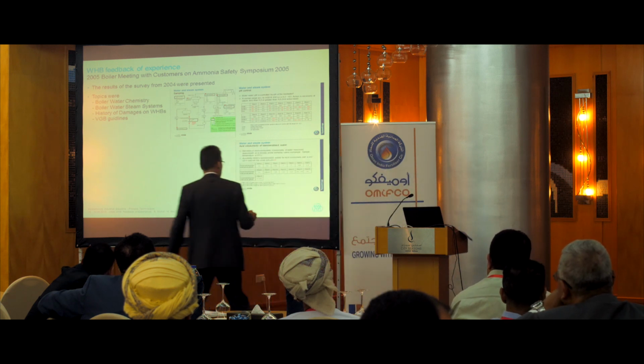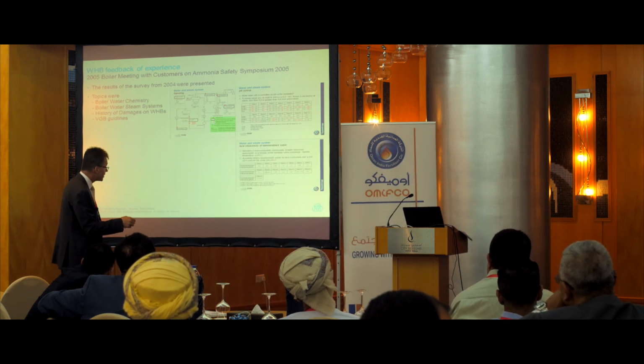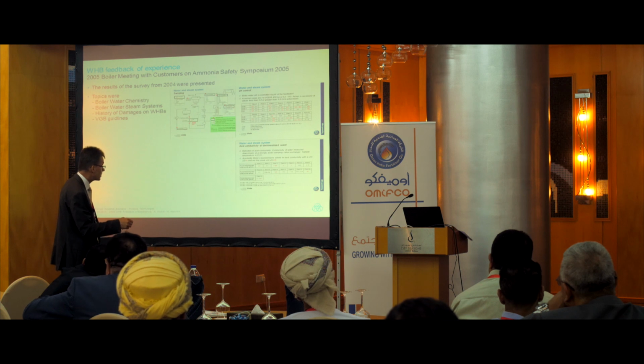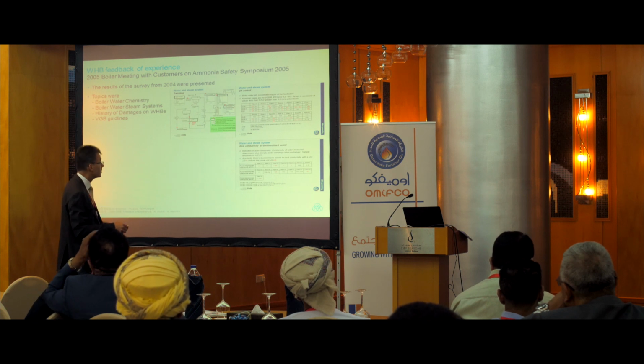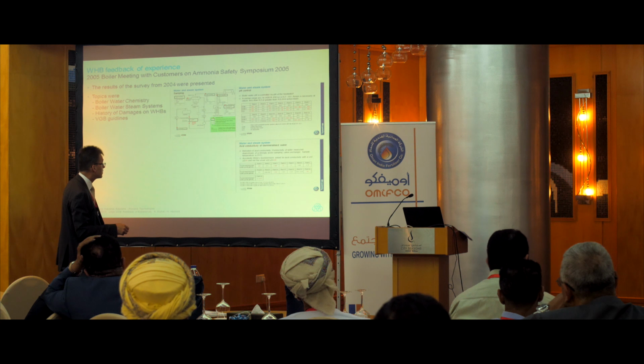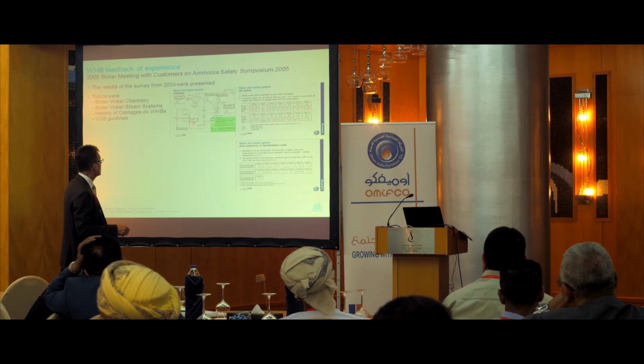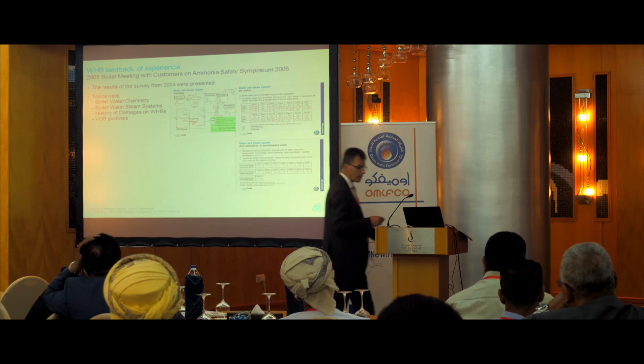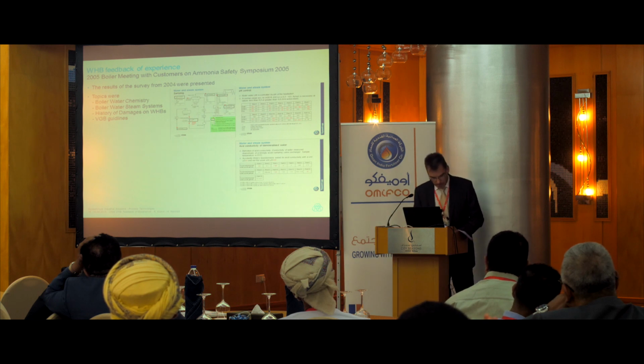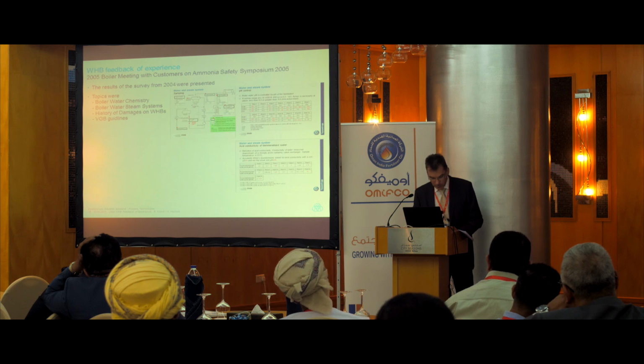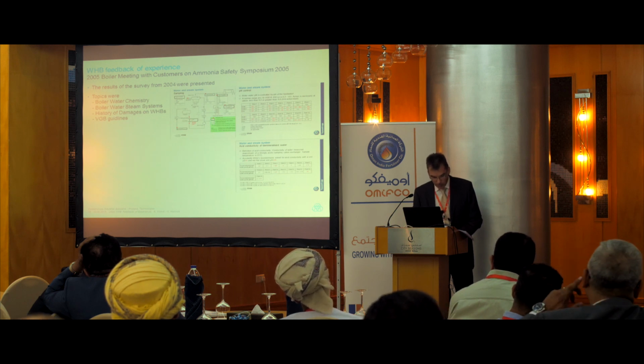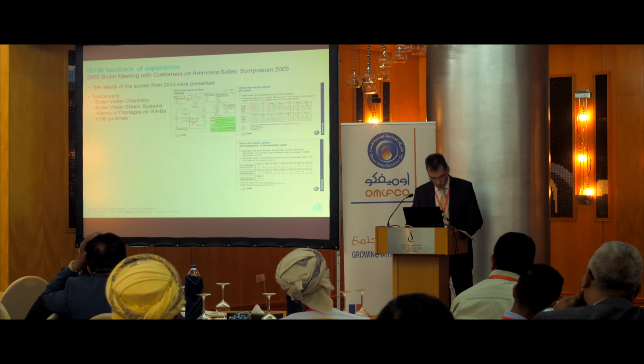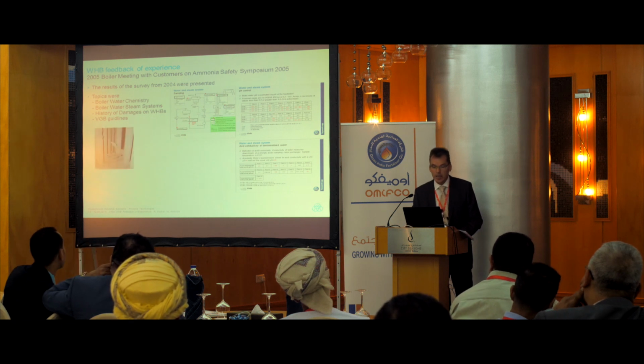And even if you cannot read the numbers, the red figures mean that in this plant something was not according to pH control, in that plant it was okay, in this plant again something was not according to the pH control we recommend. We also have differences in acid conductivity. And with the latest evidence of defective boilers which have been discussed, all had in common that there were deposits on tube sheets. Typical deposits are like this.